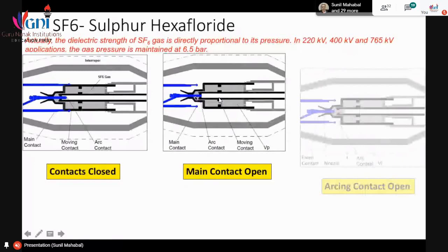It is used extensively at 220 kilovolt, 400 kilovolt, 765 kilovolt. The gas pressure maintained is 6.5 bar of sulfur hexafluoride. This is how it works. And finally, the supply reaches machines at 440 volt, again through the circuit breaker and isolators, because there is an isolating transformer in every machine which isolates the control circuit from the mains.